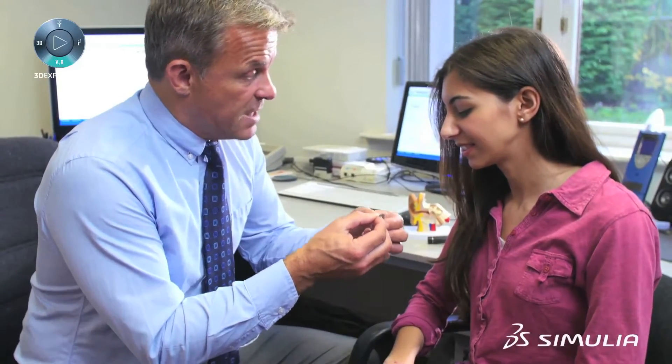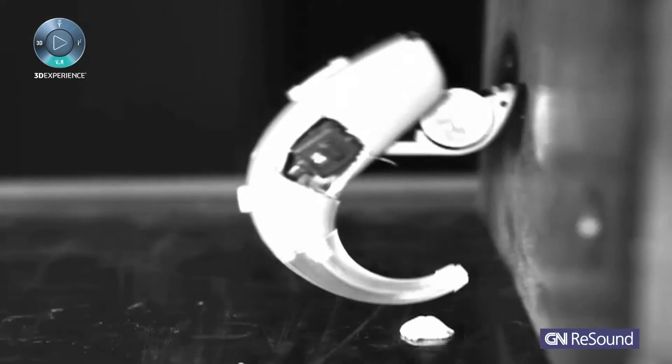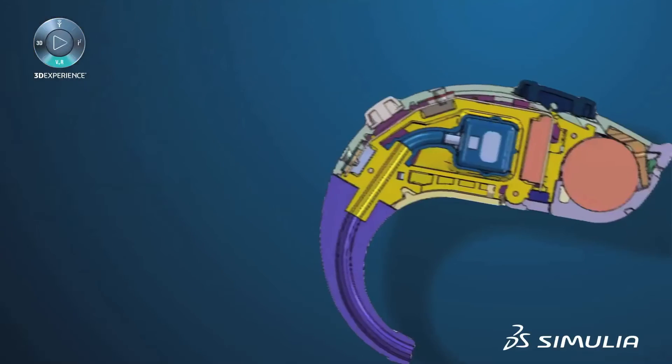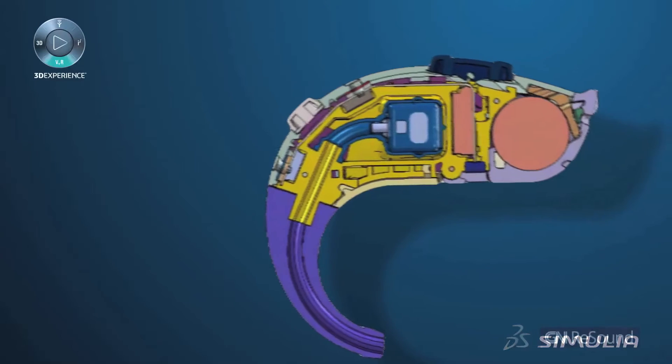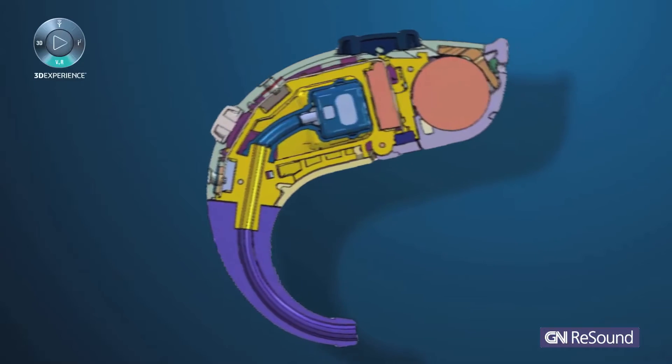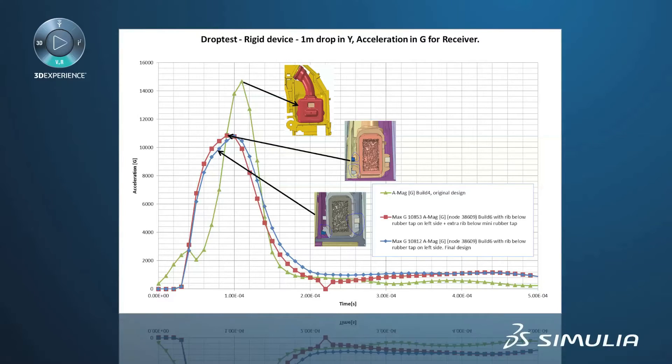The vibroacoustic simulations are the most important ones to make a good hearing aid design, but recently, since the last year, we have also done impact simulations of the hearing aid to make it withstand the drop — for example when you change the battery in the hearing aids, you can easily drop it, so we need to make sure that the hearing aid is still working after it has been dropped several times on a hard surface.